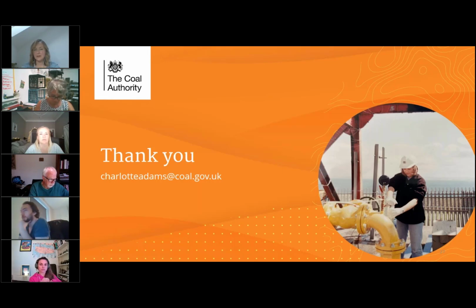For example, in Gateshead, it's not from pumped mine water, that'll be from purpose-drilled boreholes. The intention is that the mine water isn't circulated around the heat network; we just take the heat out at surface with a heat exchanger and put it back underground. We're very careful to exclude air from the system. Our biggest problem is iron, and salinity, because some of the seams we pump from are quite deep. So we make sure the wells we specify are geared up to cope with that harsh environment, and we exclude air so that ochre doesn't have a chance to precipitate. When we re-inject, we always re-inject to flooded seams, because people have asked why not re-inject to a dry seam - it'd be easier to get the water away, but we'd probably clog it quite quickly. So that's how we tend to do it.